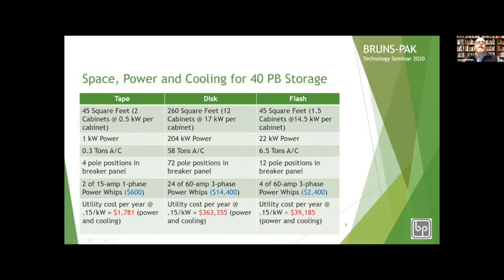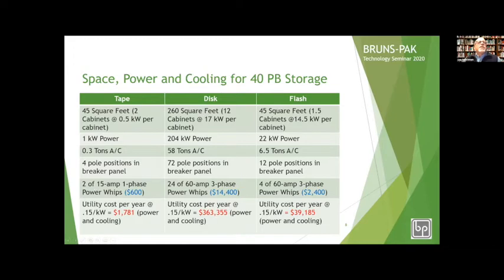When we equate that to air conditioning: it's a third of a ton for tape, 58 tons of AC for disk, and 6.5 tons of AC for flash. For breaker panel positions: tape requires 4 pole positions with minimal power whips; disk requires 72 poles, a couple of panels; and flash requires 12 breaker poles. In approximate whip costs: 2 single-phase 15-amp power whips at $600; 24 three-phase 60-amp whips at $14,400; and 4 three-phase 60-amp power whips at $2,400.